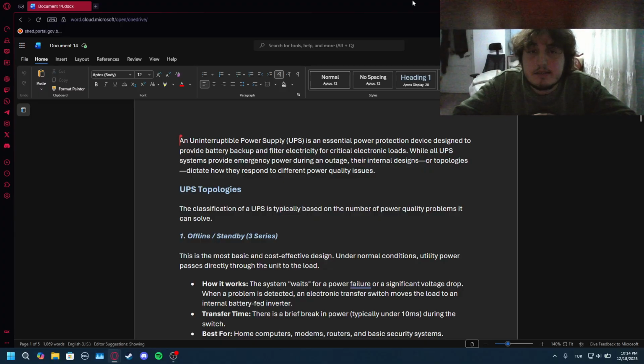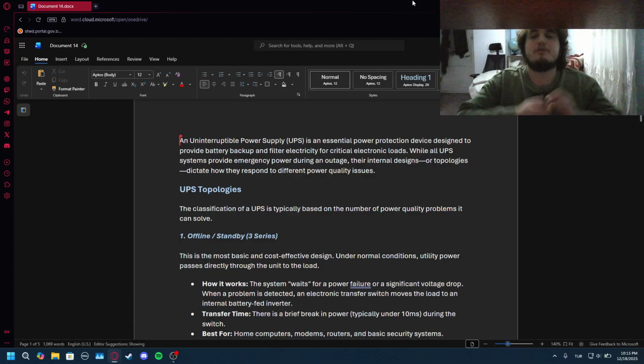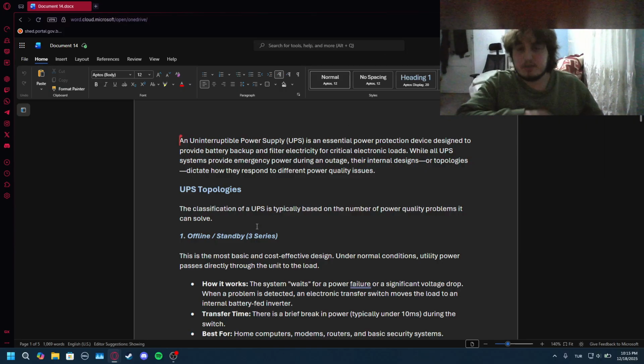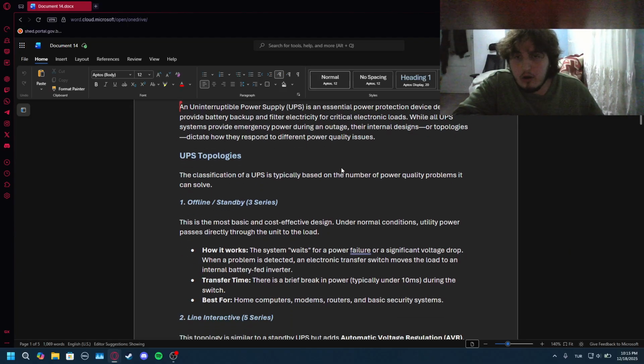A UPS is an essential power protection device designed to provide battery backup and filter electricity for critical electronic loads. While all UPS systems provide emergency power during an outage, their internal designs, or topologies, dictate how they respond to different power quality issues. UPS topologies. The classification of UPS is typically based on the number of power quality problems it can solve. Offline or standby, 3 series. This is the most basic and cost-effective design.